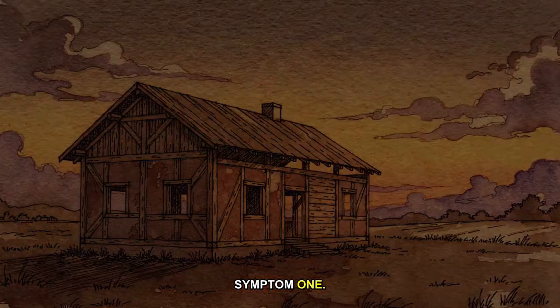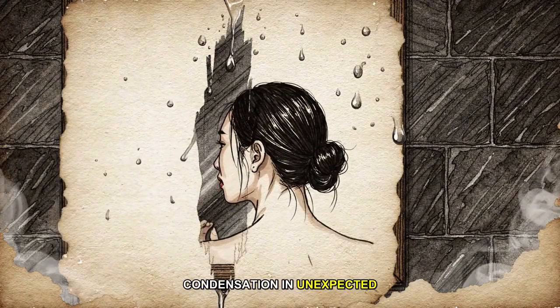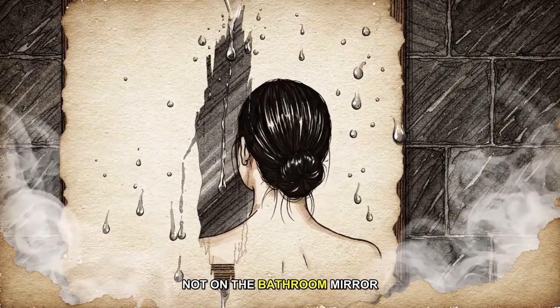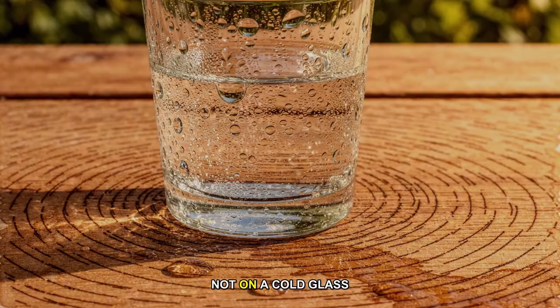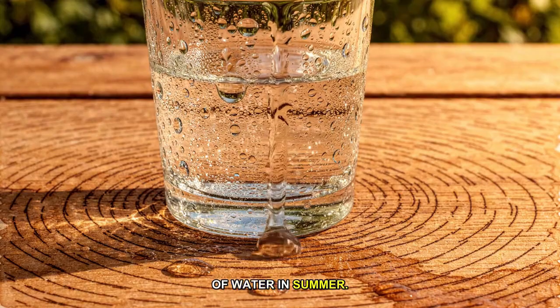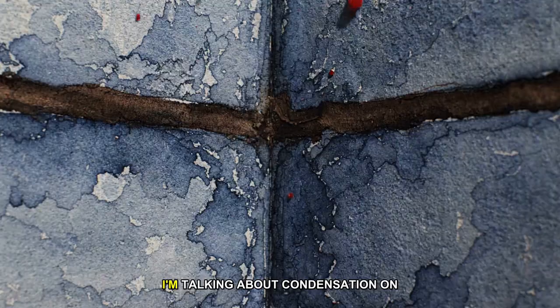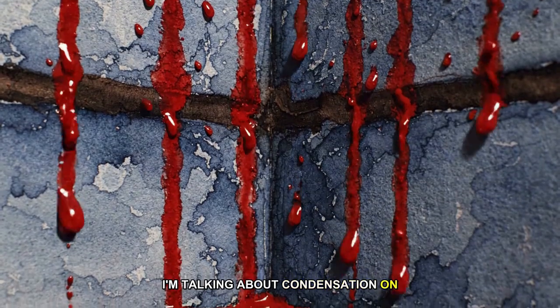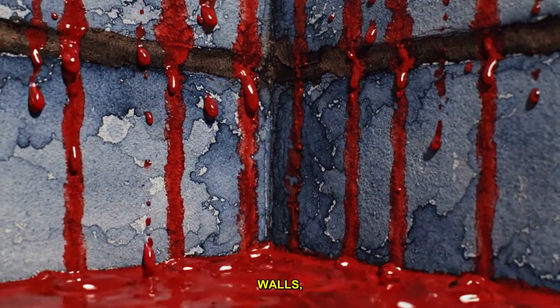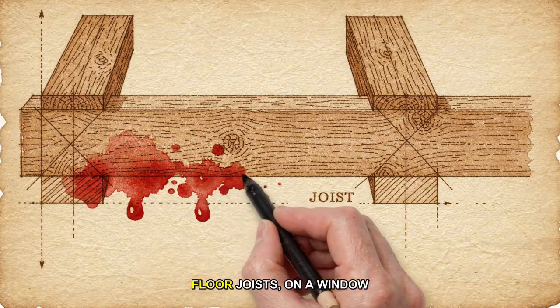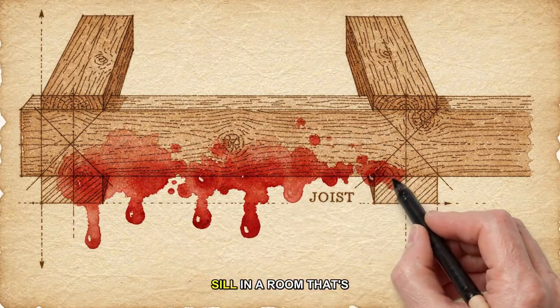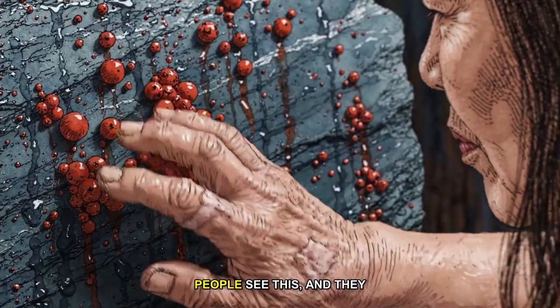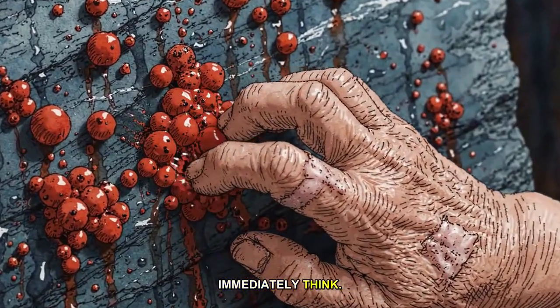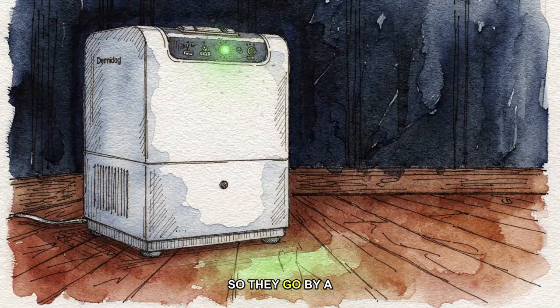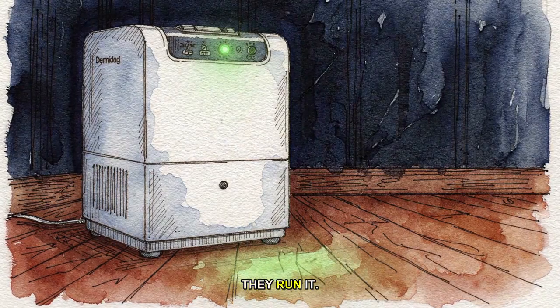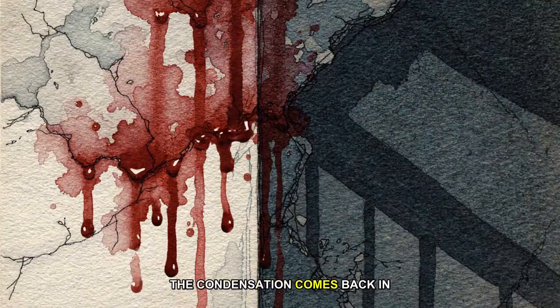Symptom 1. Condensation in unexpected places. Not on the bathroom mirror after a shower. Not on a cold glass of water in summer. Those are normal. I'm talking about condensation on the inside of your exterior walls, on the underside of your floor joists, on a windowsill, in a room that's heated. People see this and they immediately think, humidity problem. So they go buy a dehumidifier. They run it. The condensation comes back in a week.